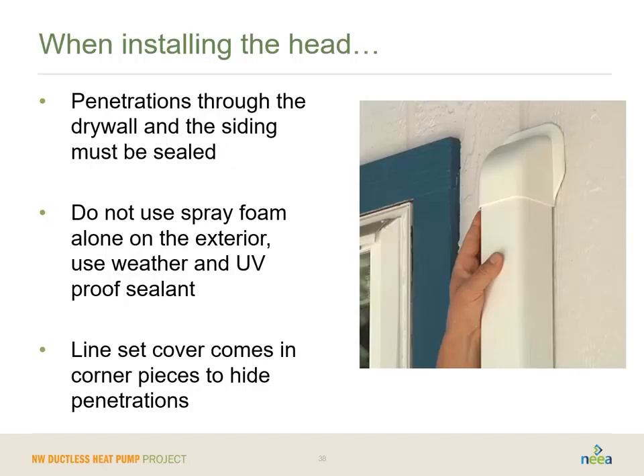When installing this head, remember penetrations through the wall are necessary for the line set and the electrical. And we really want to make sure that both the drywall and the siding are well sealed. And if you're going to use spray foam around there, that's a great idea, but make sure it is well covered from both weather and UV. That spray foam, while it's a great product, if it's exposed to UV for long periods of time, it will start to change color and eventually degrade.